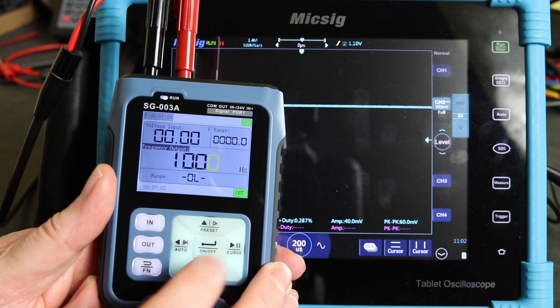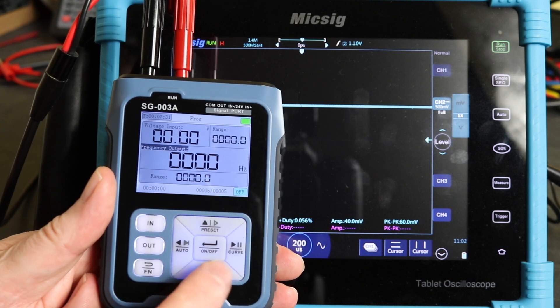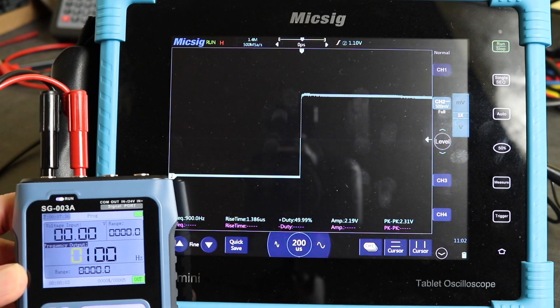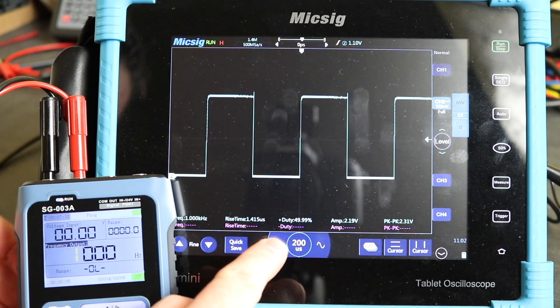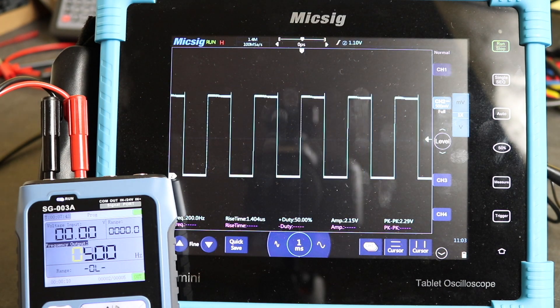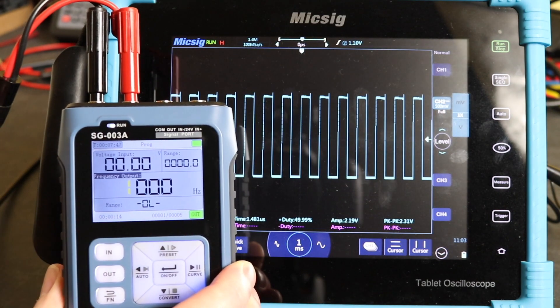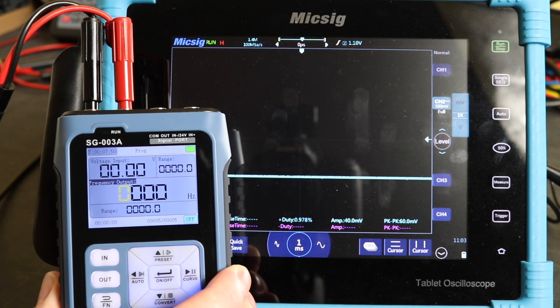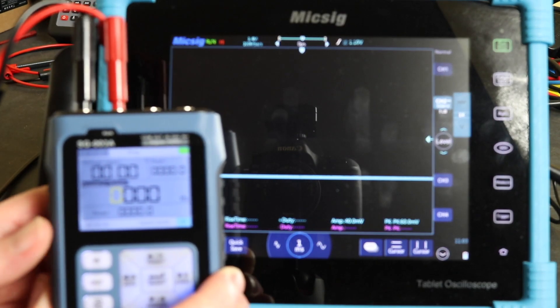To activate these programs, use the function key and then auto, then hit the on button and it'll go up and then come back down. You can see the pulse going up and down, and it counts the number of cycles remaining at the bottom. When it's done it automatically turns the output off.